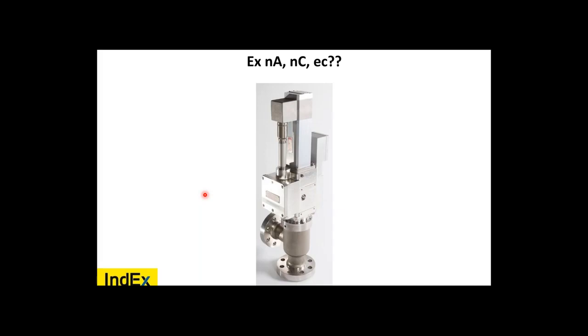Well, it's Ex nC. This one is the non-incendive, meaning it just has to be inside of a mechanical enclosure. That enclosure, has it even been tested for IP54? I'm unsure. But once you start getting into these things on the edges, which can be confusing, read the certificate, read the manufacturer's IOMs, installation, operation, and maintenance manuals.